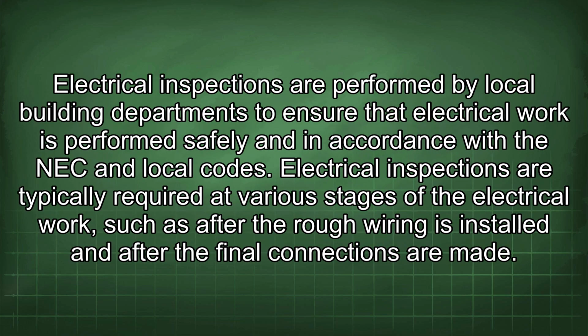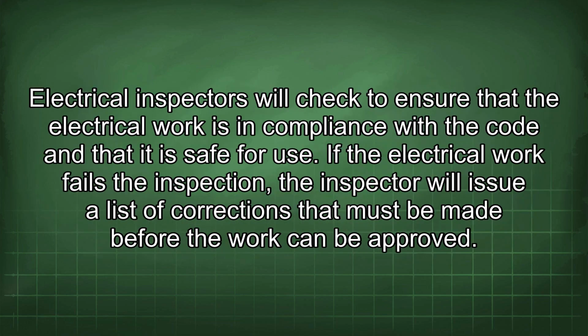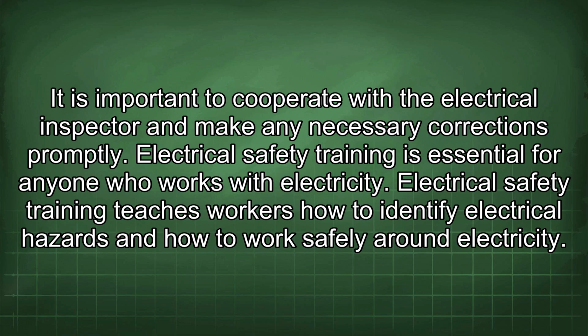Electrical inspections are performed by local building departments to ensure that electrical work is performed safely and in accordance with the NEC and local codes. Electrical inspections are typically required at various stages of the electrical work, such as after the rough wiring is installed and after the final connections are made. Electrical inspectors will check to ensure that the electrical work is in compliance with the code and that it is safe for use. If the electrical work fails the inspection, the inspector will issue a list of corrections that must be made before the work can be approved. It is important to cooperate with the electrical inspector and make any necessary corrections promptly.